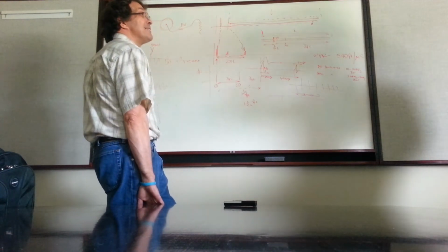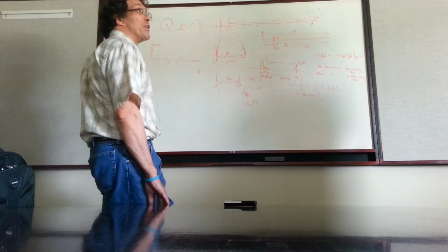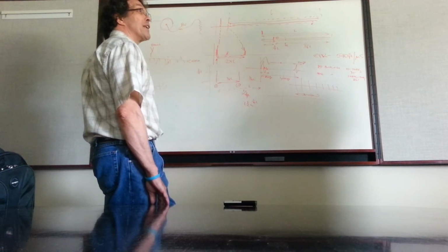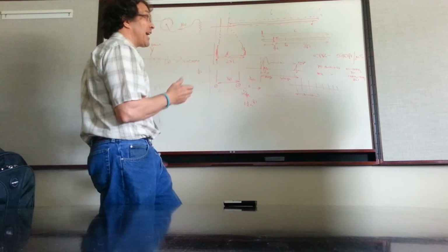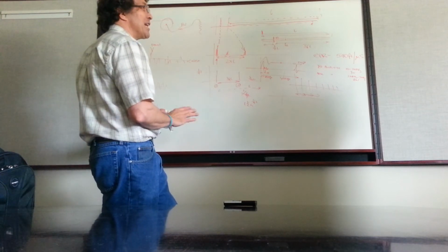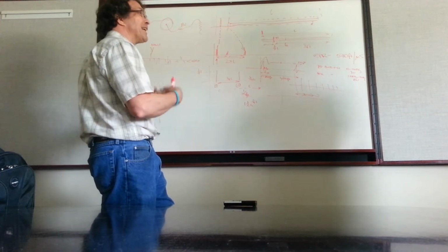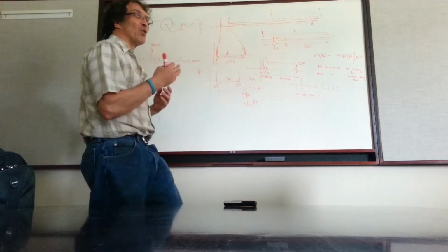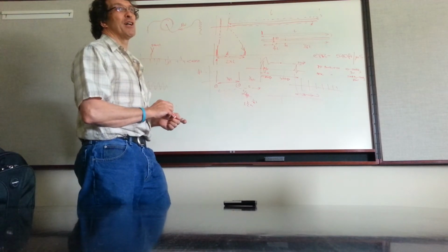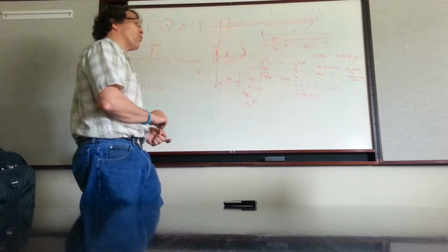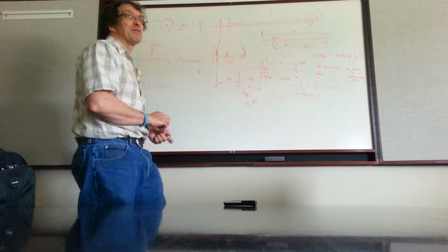I mean, the only other alternative was that fault that we saw in the middle, that kind of would come and then go, but we kept seeing that little pulse that was in the middle, and I discounted it, because generally, if it's exactly in the middle, it's not real. Unless you can keep reliably getting it, trying different things, it's always in the middle, you usually discount it, because it's a ghost reflection. But if it was in the middle, then when they cut it and took 50 feet out, they could have cut the fault out.